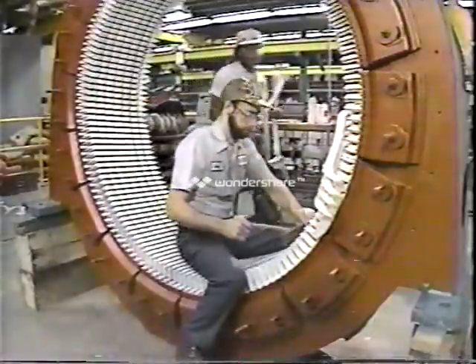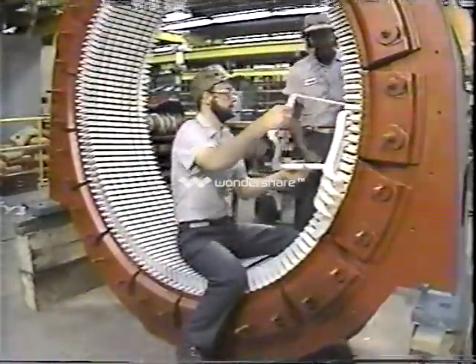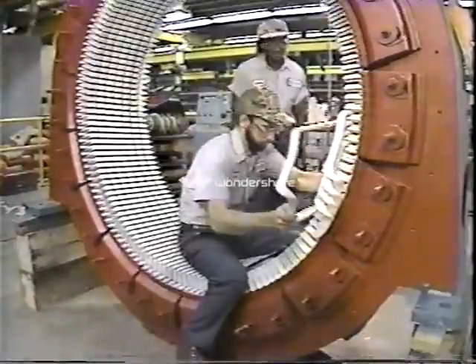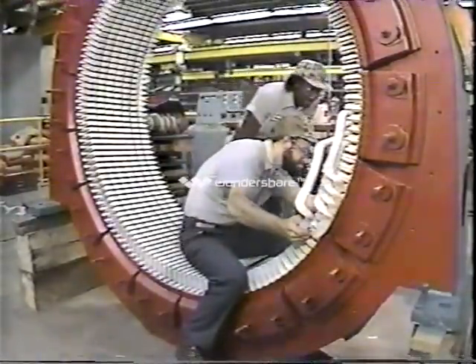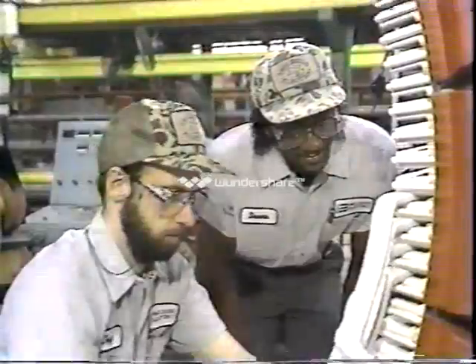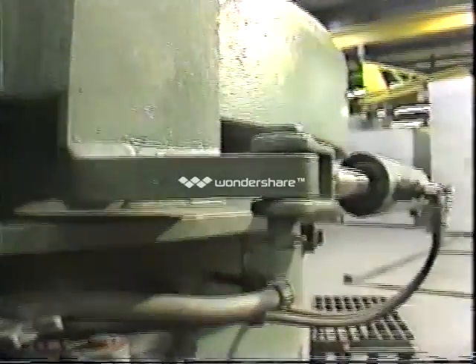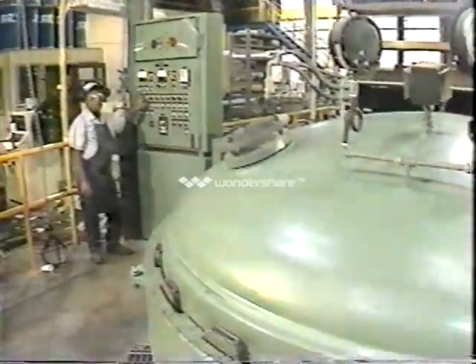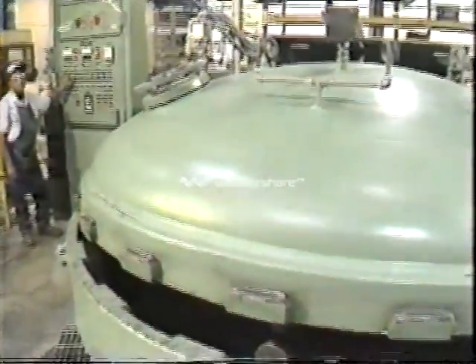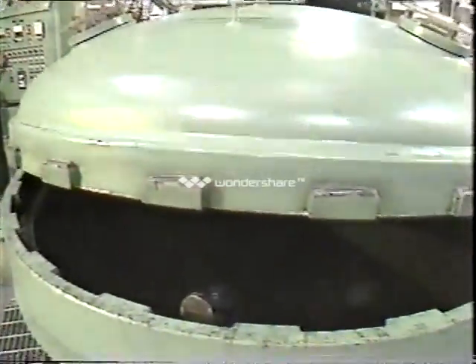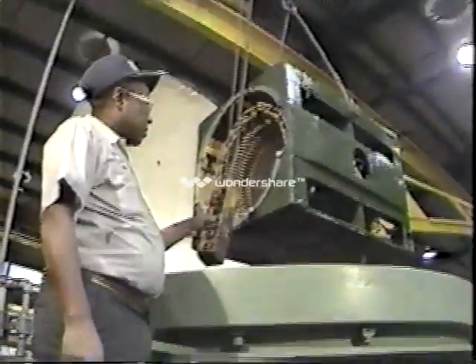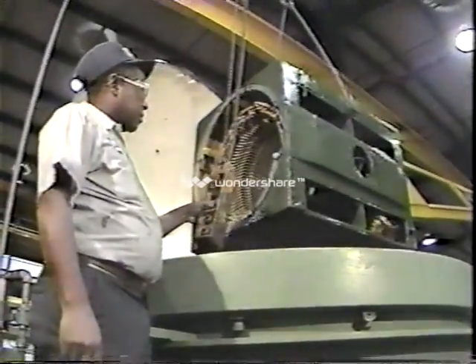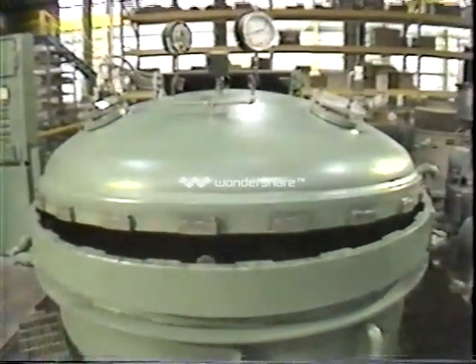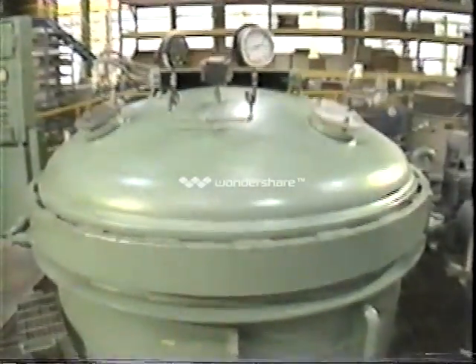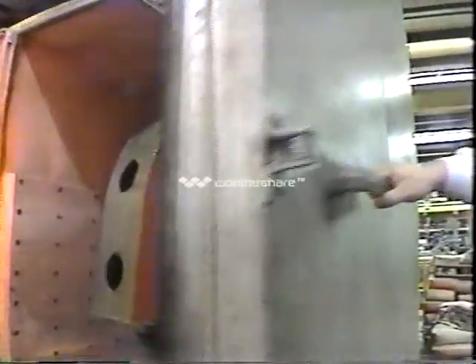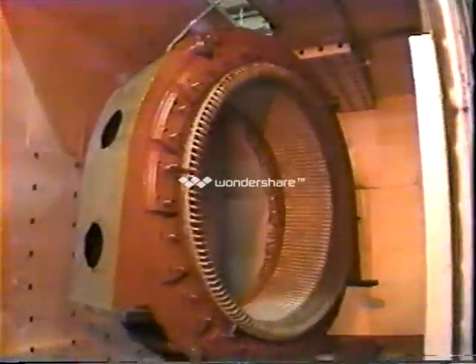Here, we're carefully installing new winding into this large stator, taking every precaution, making sure that every coil is fitted properly, giving strict attention to the technique and detail. Upon completion of rewinding, the stator is then placed into this tank. A vacuum is applied and then high pressure is introduced in order to force the liquid resins deep into the recesses of the winding, assuring mechanical strength and moisture resistance and enabling the motor to run cooler through improved heat transfer. As you can see, it gets mighty hot at Ingleside Electric.